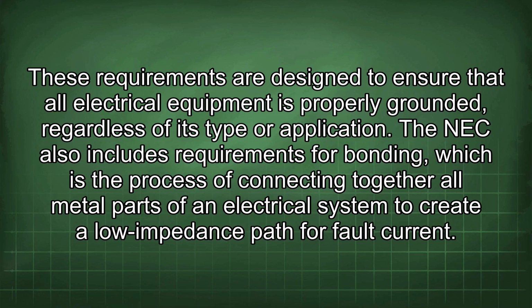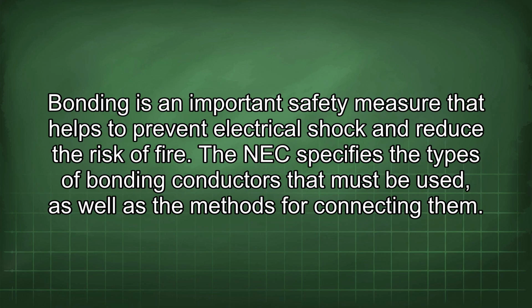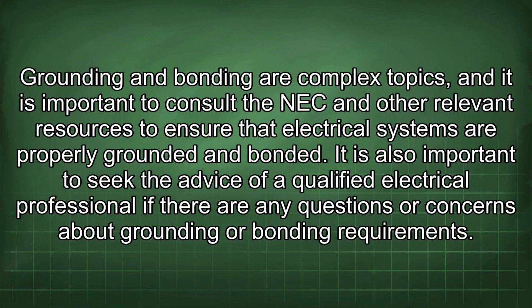The NEC also includes requirements for bonding, which is the process of connecting together all metal parts of an electrical system to create a low impedance path for fault current. Bonding is an important safety measure that helps to prevent electrical shock and reduce the risk of fire. The NEC specifies the types of bonding conductors that must be used, as well as the methods for connecting them. Grounding and bonding are complex topics, and it is important to consult the NEC and other relevant resources to ensure that electrical systems are properly grounded and bonded.